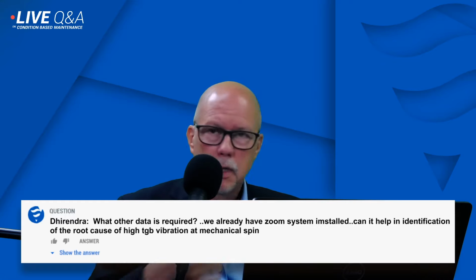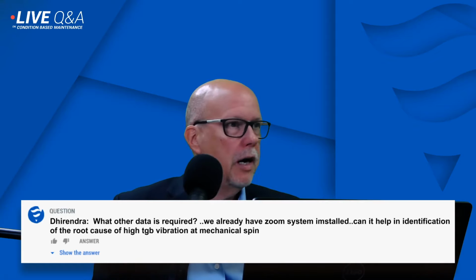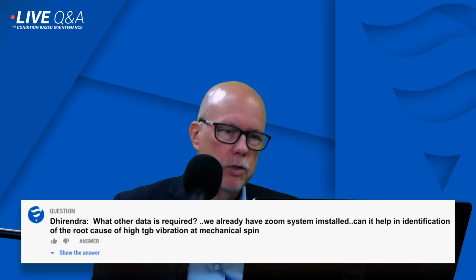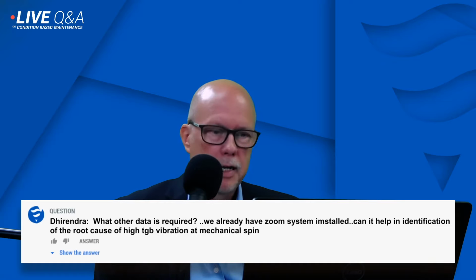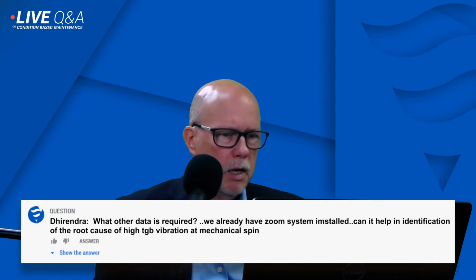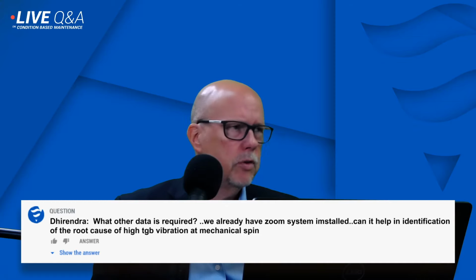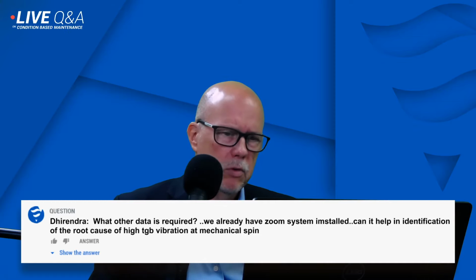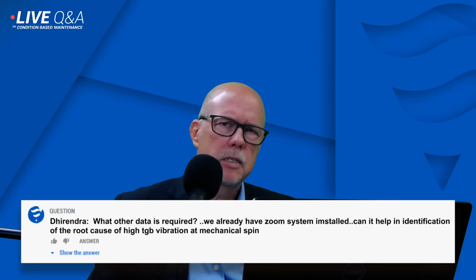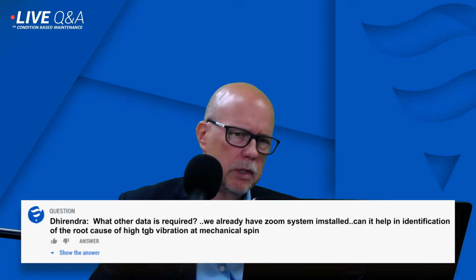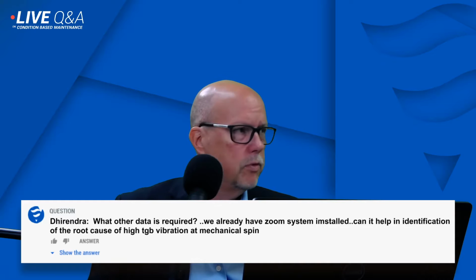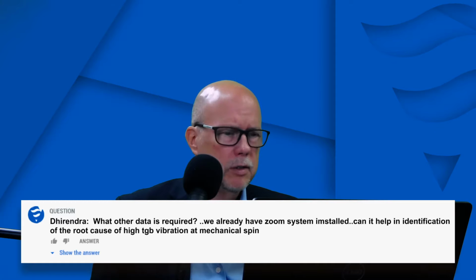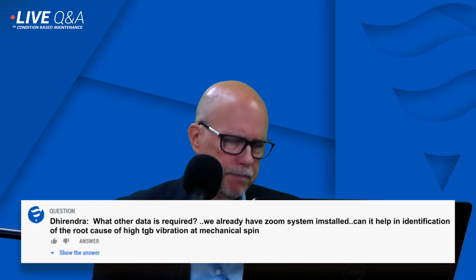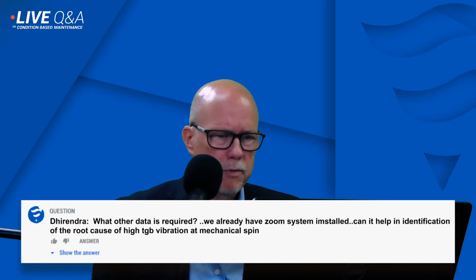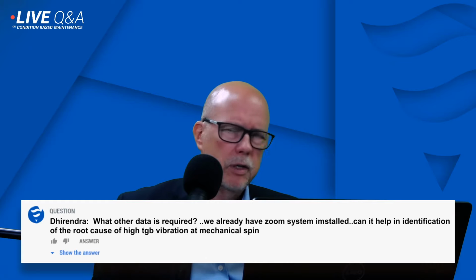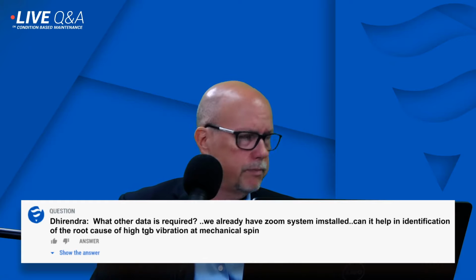I mean, if you're going to have a problem having the vibration high at speed no load and having it very low during operation, that's probably the best problem you can have, because in reality, when you're operating, there is no problem. But I am curious to see why the turbine has such high vibrations at speed no load, whereas the other bearings do not. That seems a little strange to me. So I guess I don't really have a complete answer for you, but if you want, you could get in contact with us and we could look at more information, especially since you have the Zoom system. We could take a look at a database and try to find out what exactly is going on.